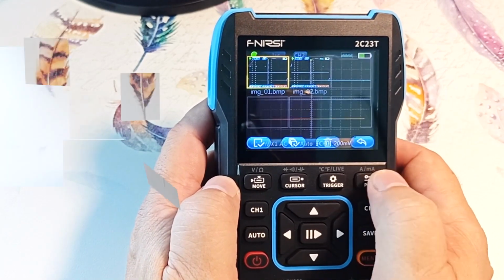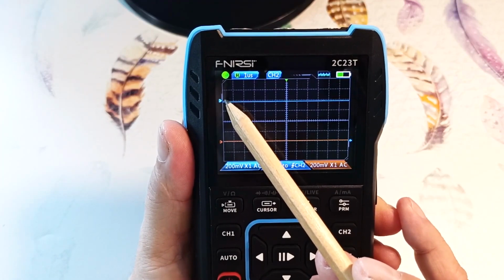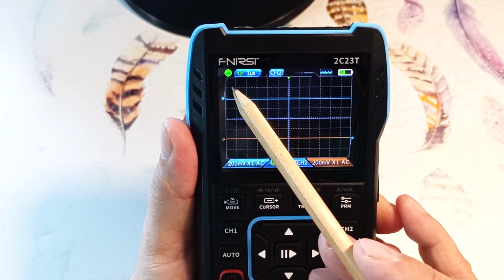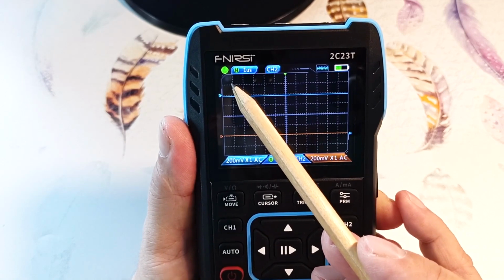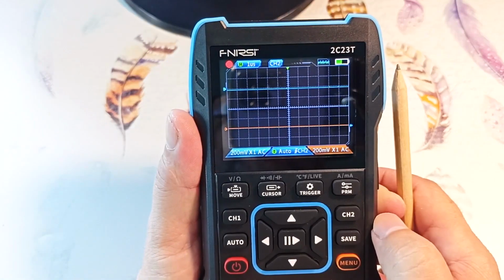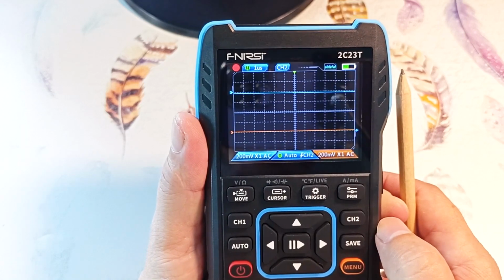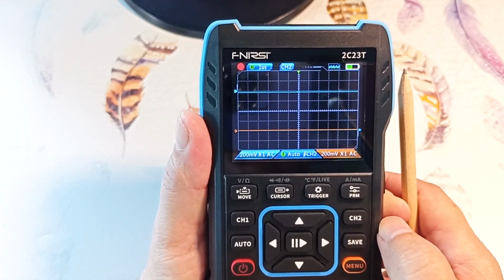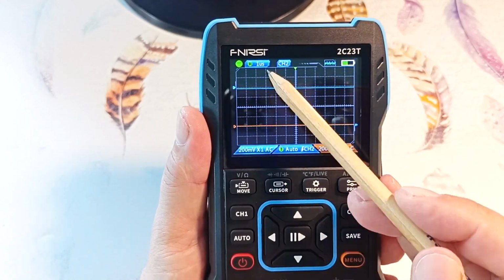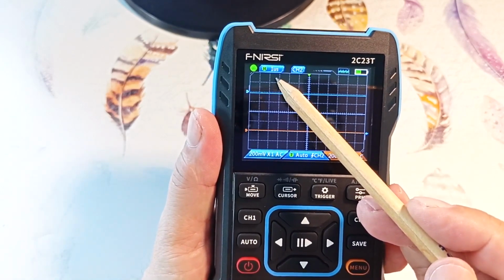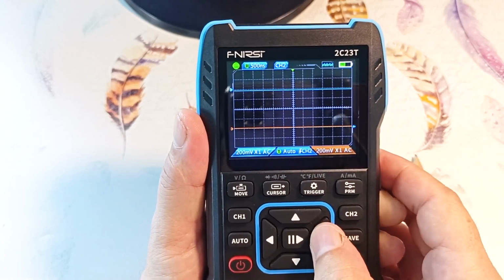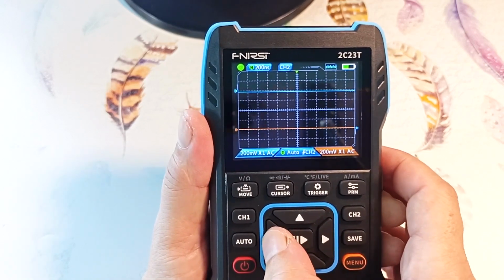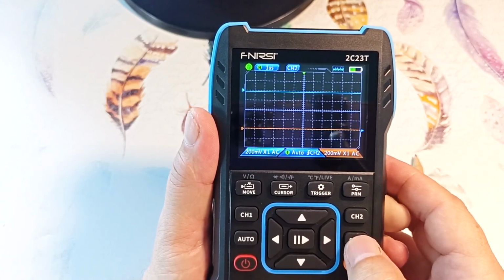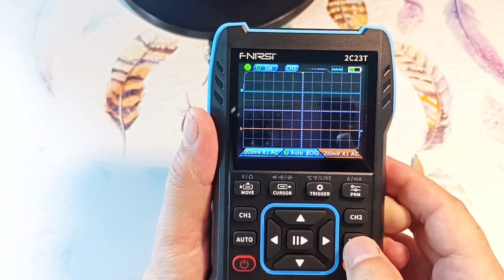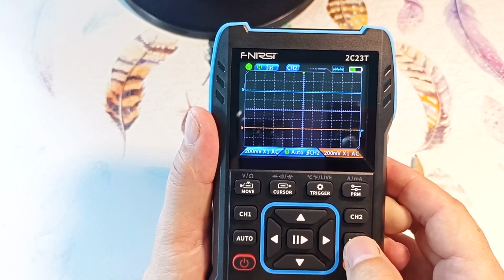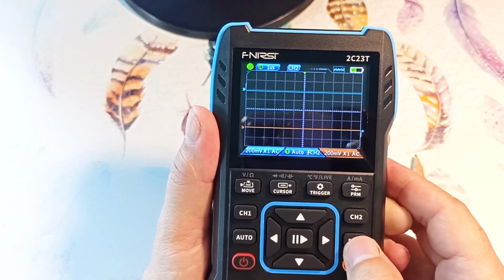We exit the mode. Let's see the values that are displayed on the screen. A green dot means the oscilloscope is in signal receiving mode. If we press the middle key of the joystick, the dot turns red and the oscillogram freezes. We're filming. The next value is the time sweep per cell. Using the left and right keys we can change this value. The time base can be adjusted from 50 nanoseconds to 10 seconds per division. The sweep frequency affects both channels at once.